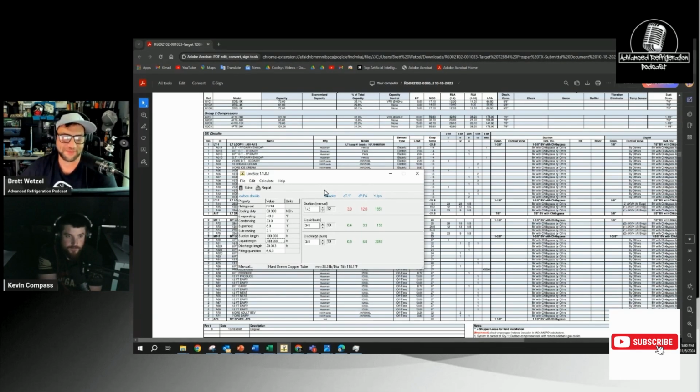I know I'm still living in theory land. But if the oil separator were to fail, where the coalescing element basically blows out, then you're going to have all this oil out in the system, and it's not going to travel back because it doesn't have that velocity kicking it out. But yeah, so you're going to have the magic oil that never leaves the compressor or the rack, except for when it does. Did it lose it? Oh yeah, all the time. Does it really? All the time.